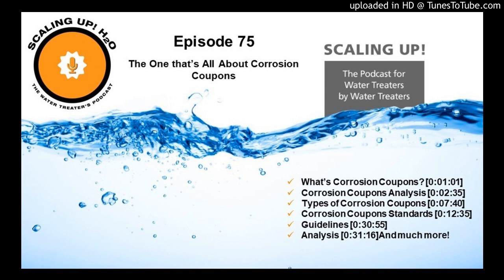To go back, general corrosion is the only acceptable corrosion that we can have within our systems. And what that means is that all of the corrosion is taking place evenly over the entire metal surface. That's what these standards are referring to. A pit means a localized point on that piece of metal where the entire potential for that entire surface is taking place in that one little pinpoint, and that's called pitting. If you see pitting of any kind, it is not acceptable.